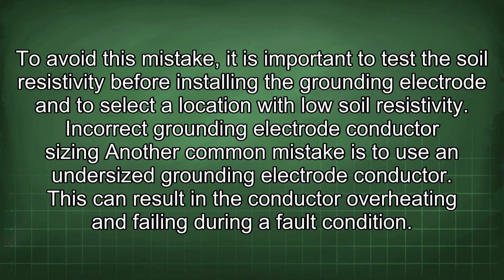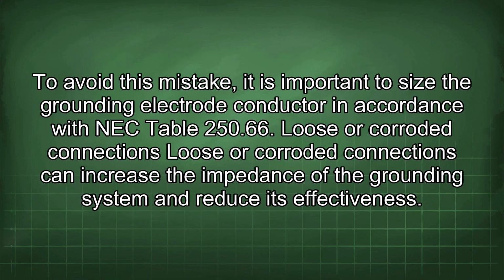Incorrect grounding electrode conductor sizing. Another common mistake is to use an undersized grounding electrode conductor. This can result in the conductor overheating and failing during a fault condition. To avoid this mistake, it is important to size the grounding electrode conductor in accordance with NEC Table 250.66. Loose or corroded connections.